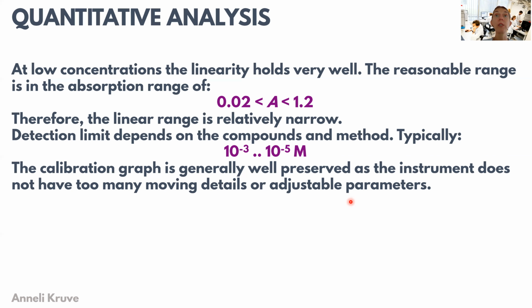What is also important is that this all is valid only when the instrument has warmed up. So this means that immediately when we plug the instrument in and put the lamp on, the lamp will start heating. And during this time, when the stable temperature of the lamp is not achieved, then the radiation intensity of the lamp and the radiation profile of the lamp will change. And this is not super good for quantitative measurements as well.